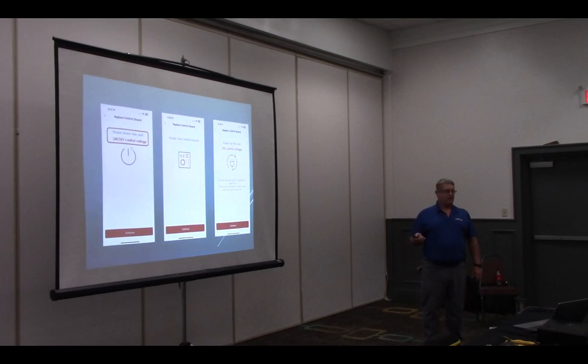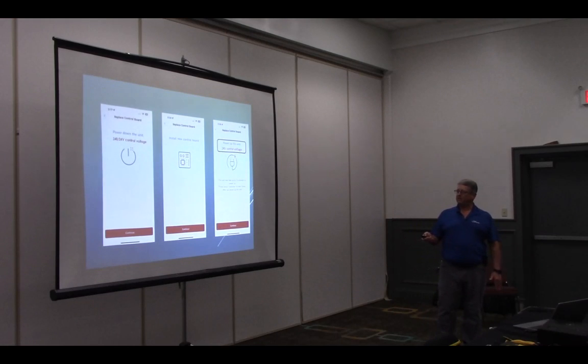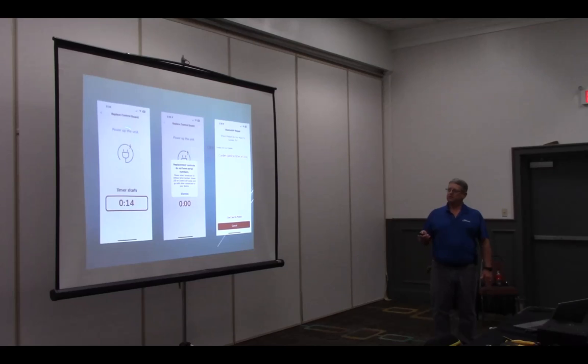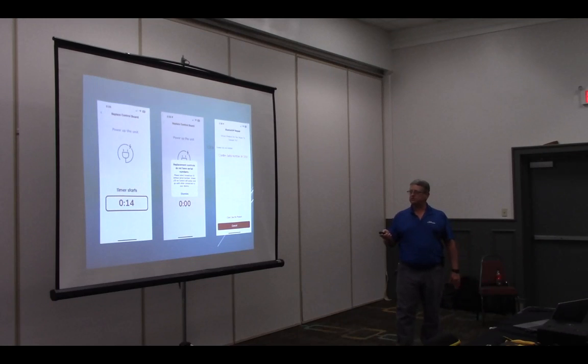If you have a bad control board, change the board. But if we're just updating software, we're going to pretend we changed the board, right? Change the control board, power everything back up, hit continue. You're going to start a 15-second timer. When that timer ends, you're going to get this message: Replacement controls do not have serial numbers. Hit dismiss. Okay? Because if you put a new board in, it's blank, right? Doesn't have any serial numbers in it. It dismissed.